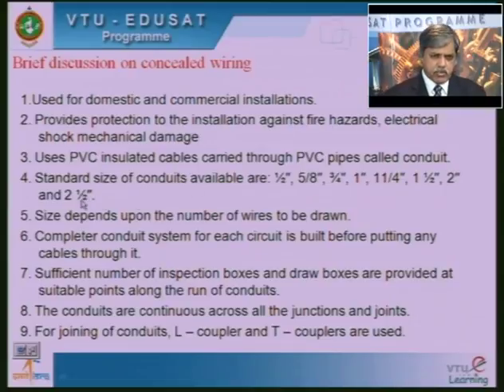So these are the sizes. Normally the tube diameter will be represented by this. Now there will be different lengths. If I want to have an extra length, I can add up 2 conduits to make a larger length. The size depends upon the number of wires to be drawn. I cannot use the same conduit of half inch to draw around 10 conductors, it is not possible. Therefore I go for a larger cross section or larger size. So I say the size depends on the number of wires to be drawn.